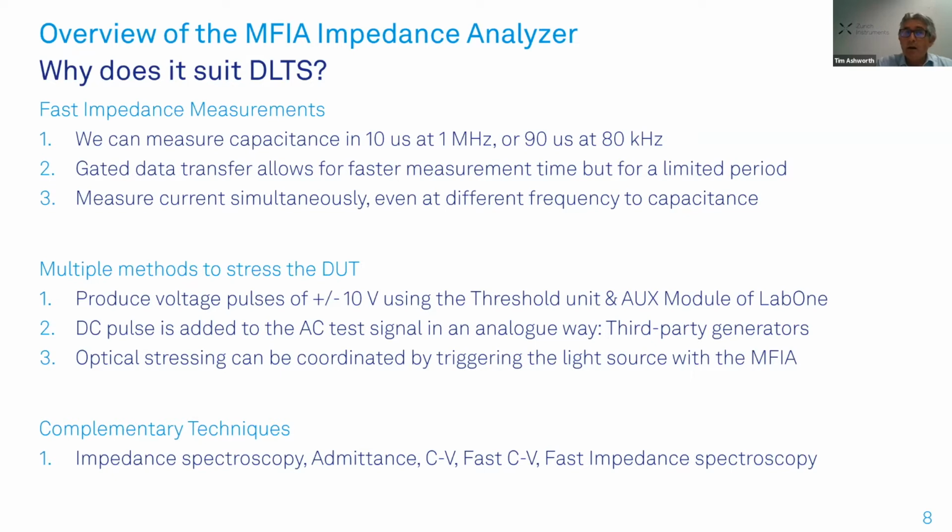And thirdly, if you want to use optical stressing, so a laser light, you could trigger that light source with the MFIA, or you can trigger the MFIA with the light source. So we have both triggers in and triggers out.